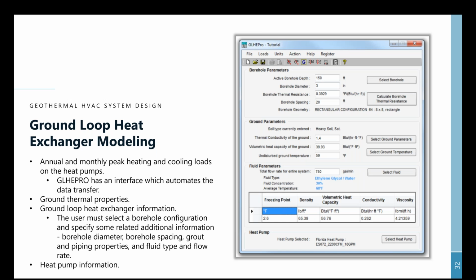With the modeling software, you're also entering all of the ground thermal properties. These are the properties that you will have received based on the testing that you've done on site. And then you start to enter the information about the ground loop heat exchanger. So you're selecting borehole configurations, determining the borehole diameter, spacing, the properties for your grout, your piping, and the properties for your fluid, you're establishing flow rates, and then you're also inputting specific information about the type of heat pump that you're going to be using.